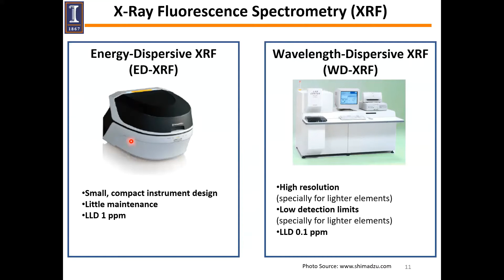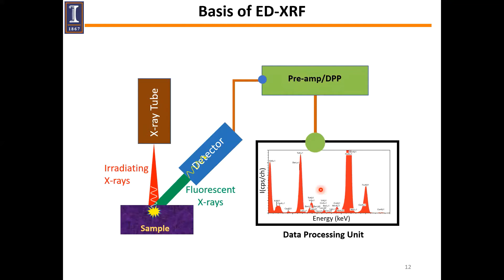Okay, here are the basic components of energy dispersive XRF. We have an X-ray tube. When the X-ray tube generates X-rays, these X-rays hit the sample, which generates the fluorescence, and the detector detects the fluorescence. Then the signal is amplified by a preamplifier, and the data is displayed in the processing unit.